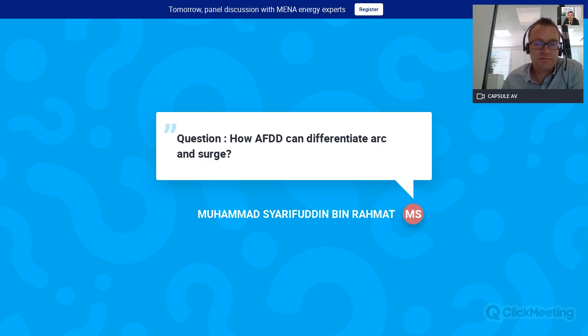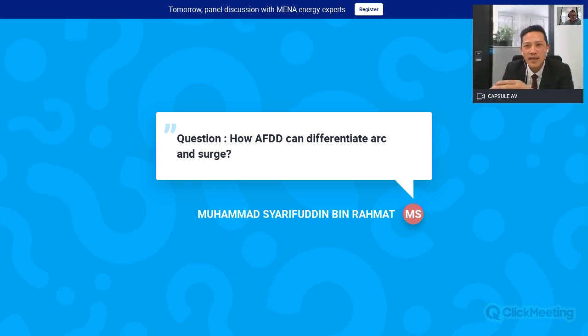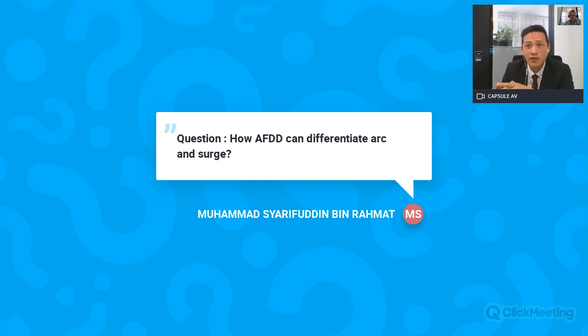Yeah, to complete a little bit, Nicolas, thank you for your explanations. The surge, as you explained, is very short and transient, like over voltage or over current. And the arc, serial fault or parallel arc fault here for AFDD, is typically a specific waveform, repetitive but irregular, like Nicolas explained. It's a combination of all the different characteristics. So the difference as well to the surge or to the short circuit is that the arc happens not over a whole half cycle, only a part of a half cycle, but it is repeated. It's not a complete breakdown, but it's a breakdown and then the insulation recovers and then it's repeated again. So it's quite specific, serial arc fault and parallel arc fault.